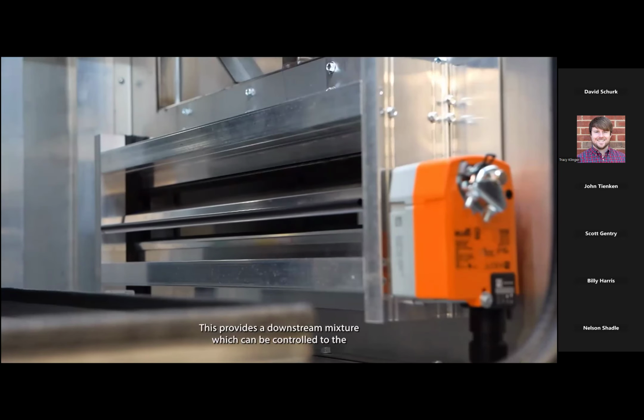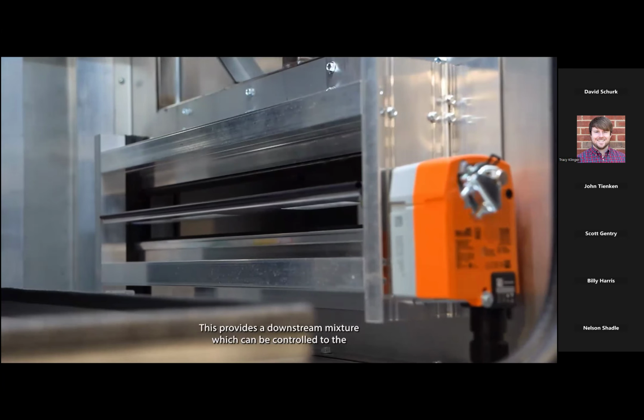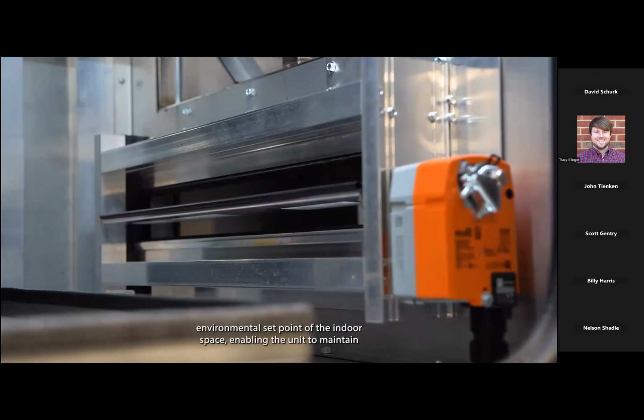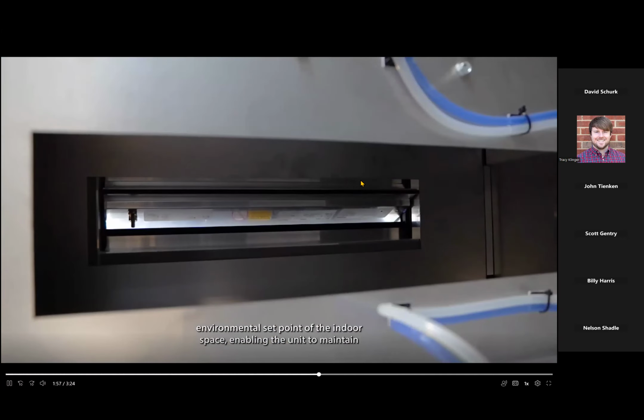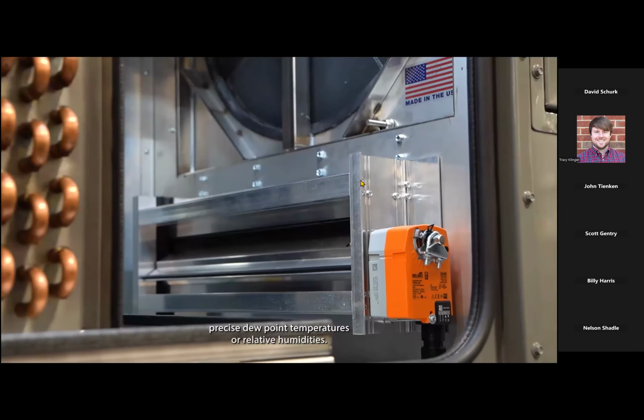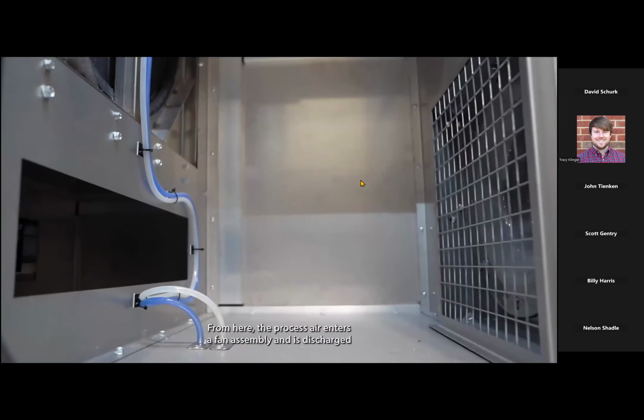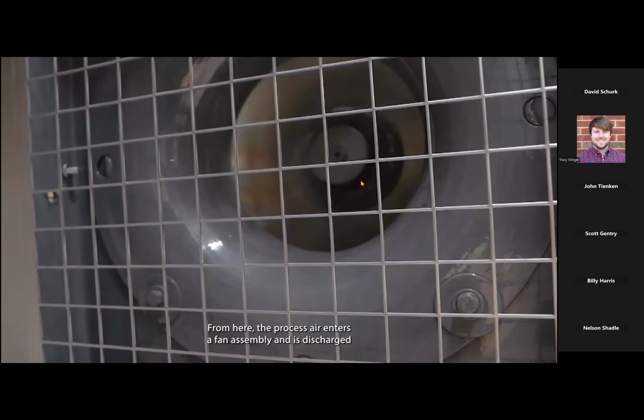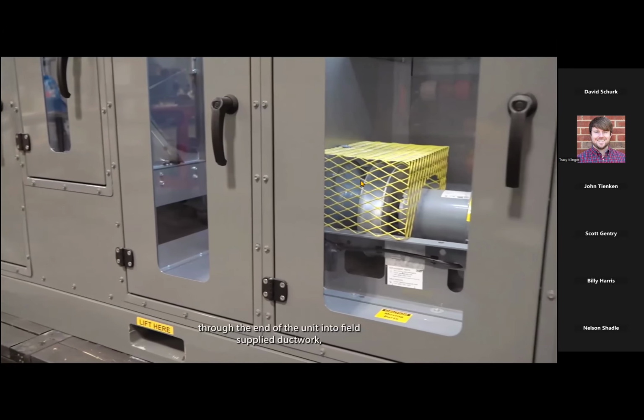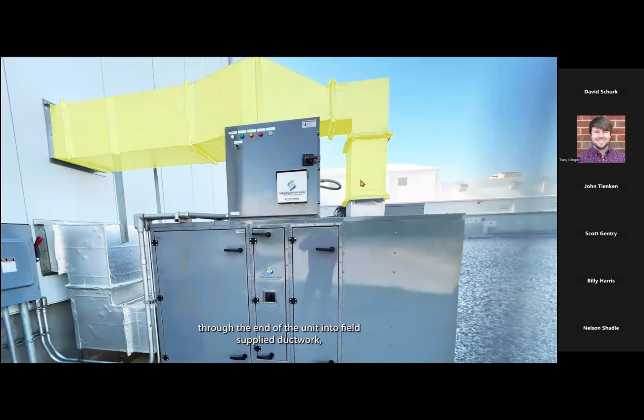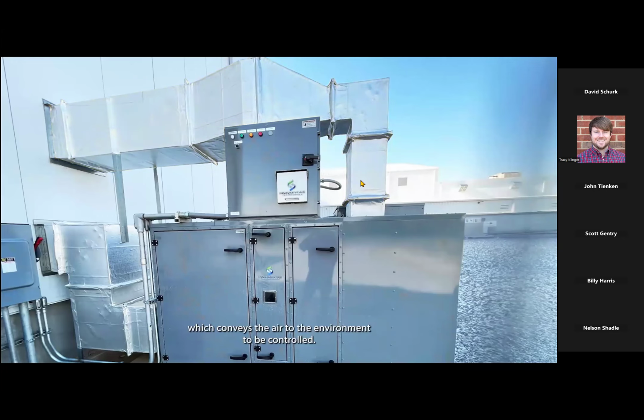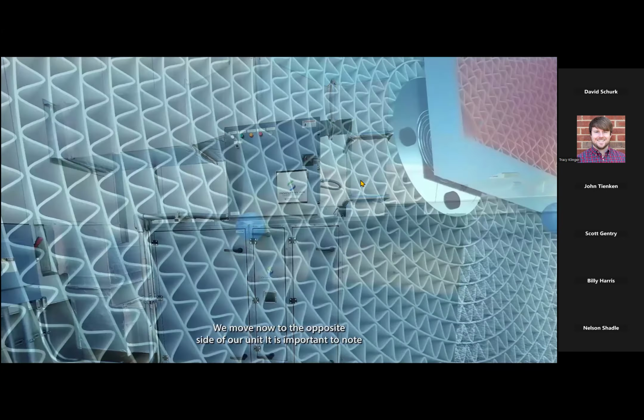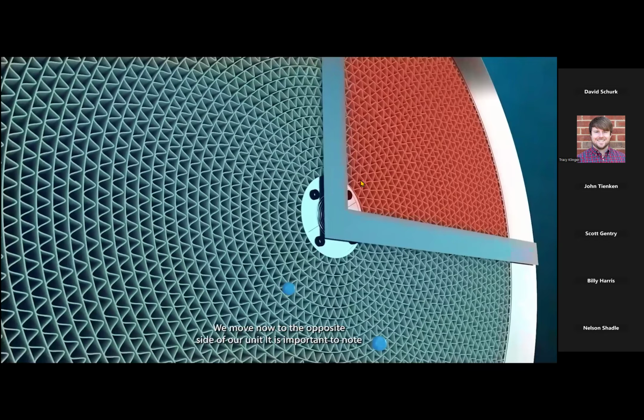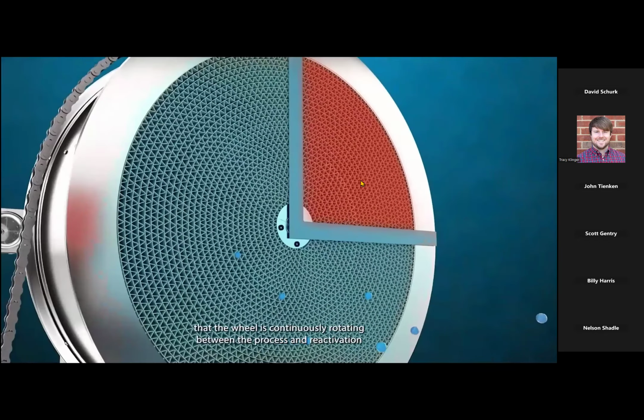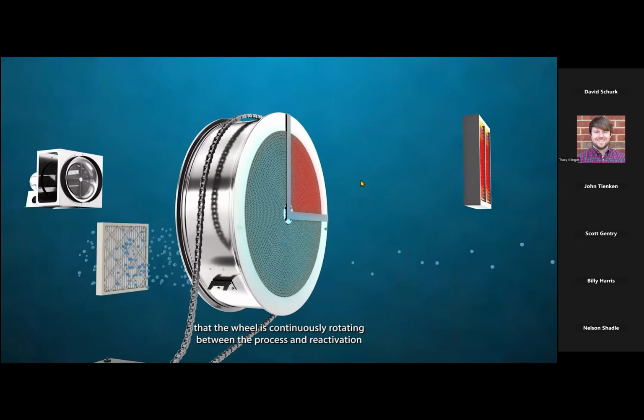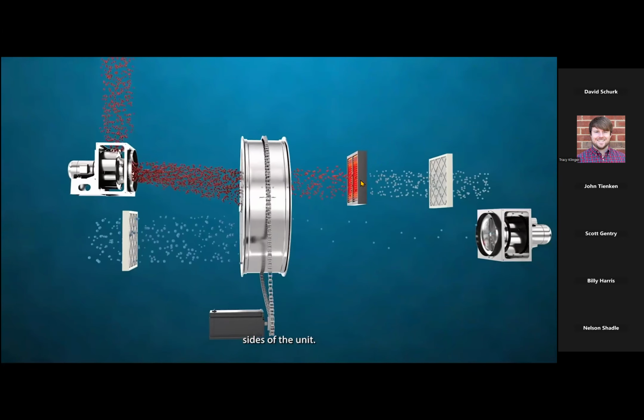This provides a downstream mixture which can be controlled to the environmental set point of the indoor space, enabling the unit to maintain precise dew point temperatures or relative humidities. From here, the process air enters a fan assembly and is discharged through the end of the unit into field-supplied ductwork, which conveys the air to the environment to be controlled. We move now to the opposite side of our unit. It is important to note that the wheel is continuously rotating between the process and reactivation sides of the unit.